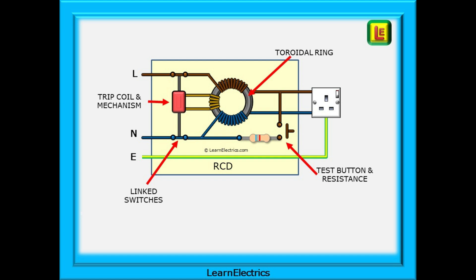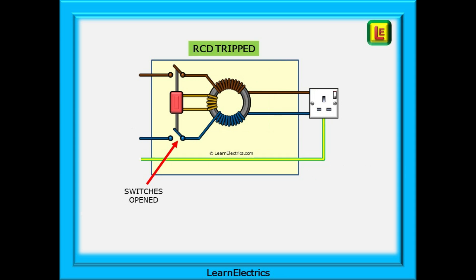Every RCD device will have a test button. Pressing this button puts a known fault current on the device that imbalances the toroidal core and simulates a fault. When the RCD detects a fault current above its preset value, the trigger mechanism will operate in fractions of a second and open the switch contacts, isolating the downstream parts and making the user safe.